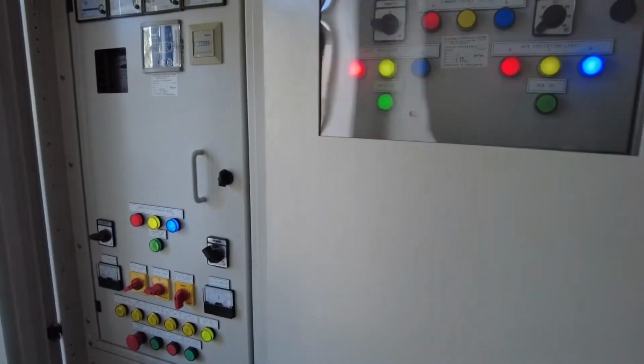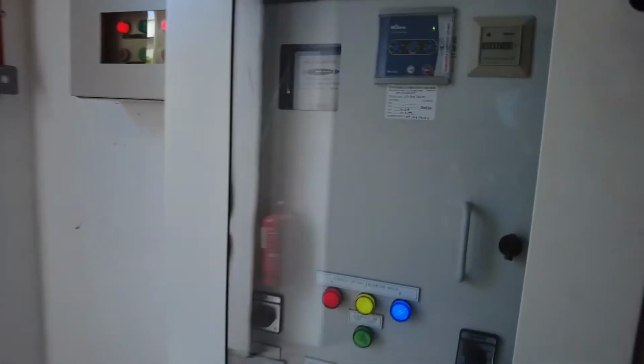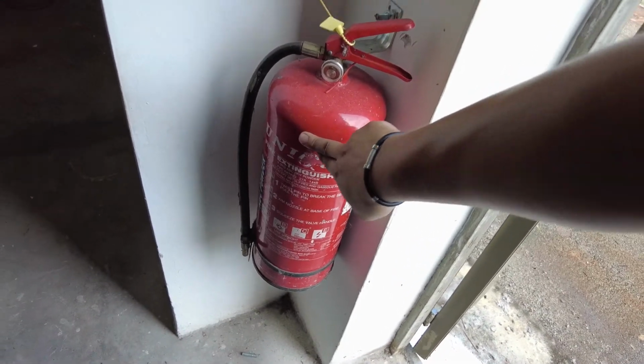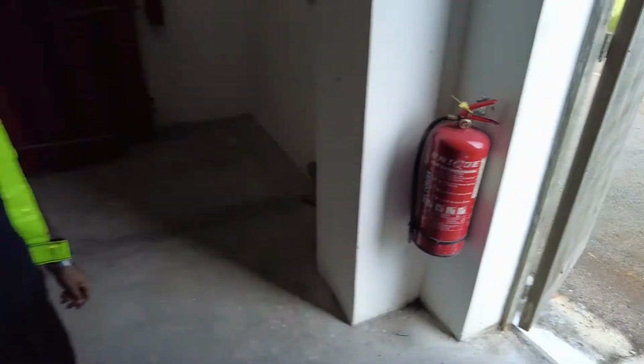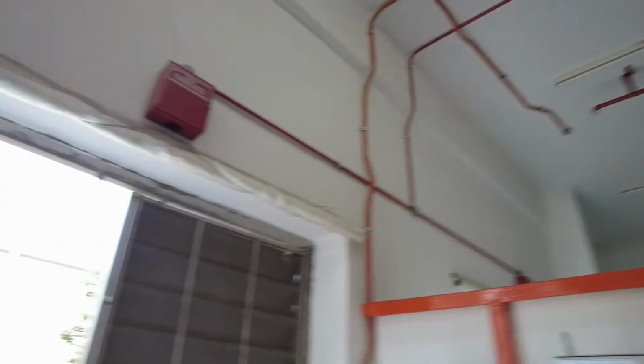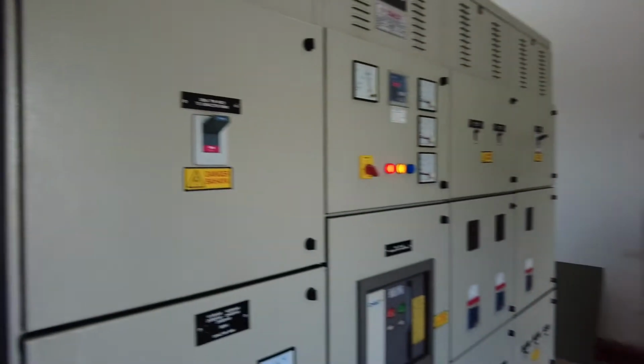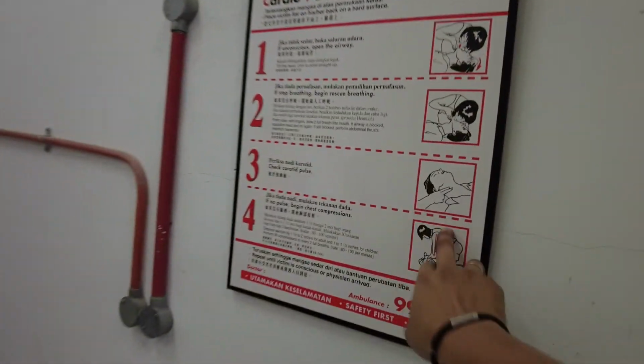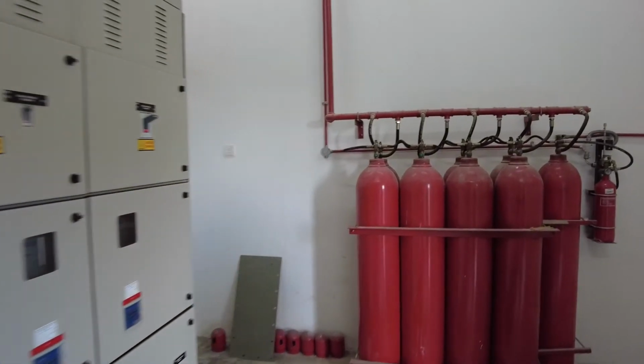Okay, as we allow the genset to stop automatically by itself, we will check the HV room first. And always remember, this is an ABC fire extinguisher, cannot put in, must use CO2. Okay, let's have a look at here. Got pressure behind, no water leaking, rubber mat in place. Okay, the room lights are okay, fire curtain okay. Alright, first aid chart in place, but there's no schematic single line drawing, and also Borang B is not affixed here, but it's affixed at the genset side.